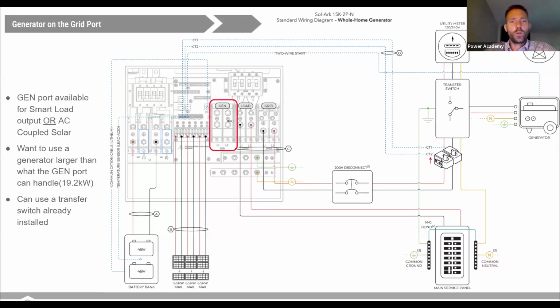So I think I used the example earlier about having a pool heater, a pool pump, or a spa pump, heaters, etc., that you might not want to power during a grid outage. Well, you can put them on the smart panel, a sub panel coming out of the gen port, and then just have that sub panel shut off anytime the batteries are not at, pick a value, 90% state of charge. That's programmable in the Sol-Ark. So if you're running off batteries and there's not excess solar, you could drop those loads off. But you might want to keep those on if you've got plenty of excess solar and your batteries are topped off and just floating. And so using the gen port as a smart loads port is a nice option. The downside to that, of course, is you do have to buy that transfer switch.